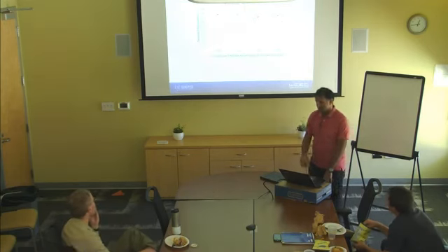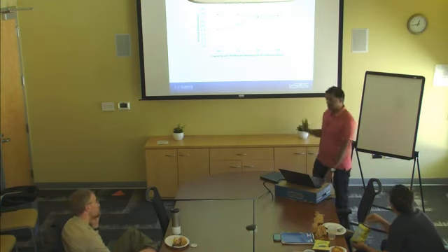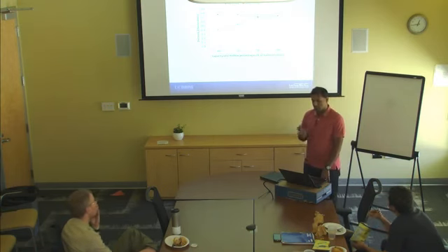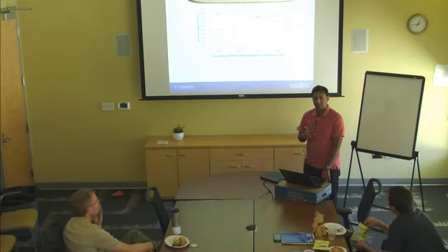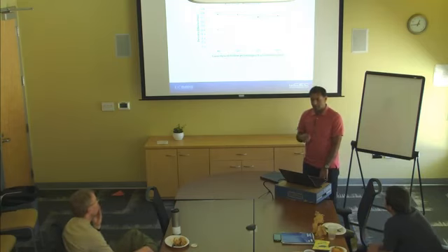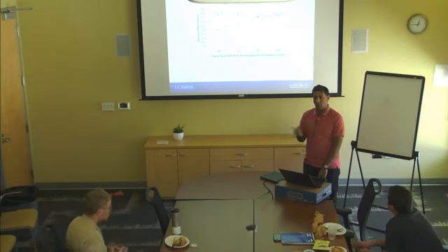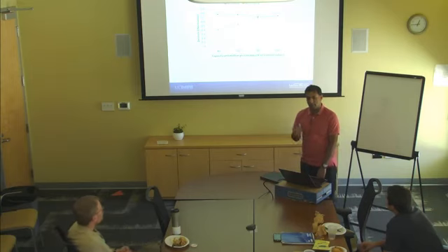And then now looking at zoned operation. Clearly the problem of distribution efficiency, distribution losses, needs to be addressed. There are a few ways that we could do that. One is to increase the insulation level of the ductwork, so R6 can be increased to R8. Another possibility is to locate the ductwork in a conditioned space so that the heat gain in the ducts actually goes down.